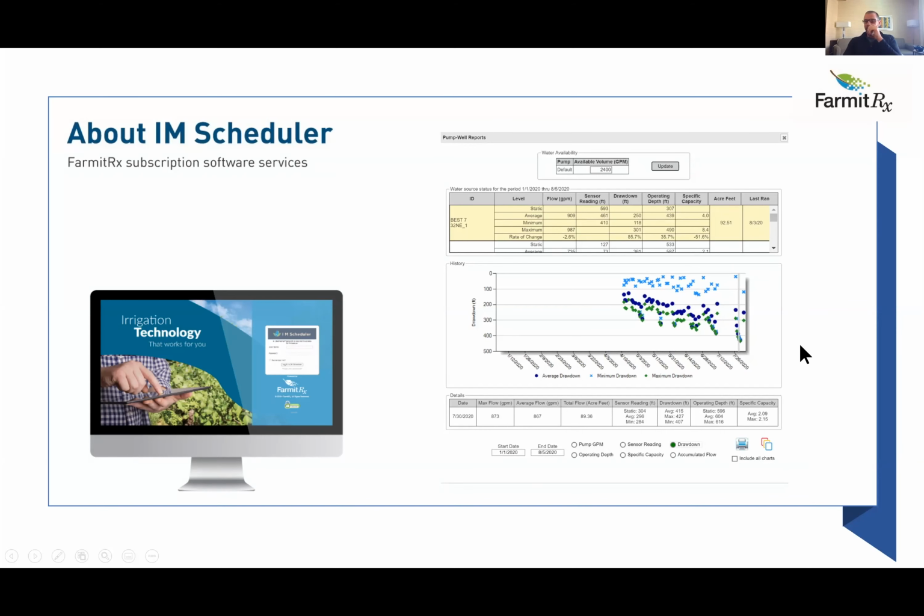In addition, and this is all provided on Wisecon system, we also provide pump monitoring in real time so that we can determine, in our case, what we're looking for in this instance is rate of change of flow, of which you can see there's very little change in flow. Now, most growers use flow meters, but the purpose of our system is to provide information as to whether or not you're going to have problems with this well, and before it goes bad on you, that you're able to address that issue. Now we're seeing in this well, we're getting lower and lower drawdowns as we're going through the season. And so this is something where the drawdown has changed significantly since the beginning of the year, and something that the grower needs to be aware of, because they're actually considering drilling some more wells out here. And I think that based off of this information, we're going to have some other type of remedy to deal with what we need to deal with.